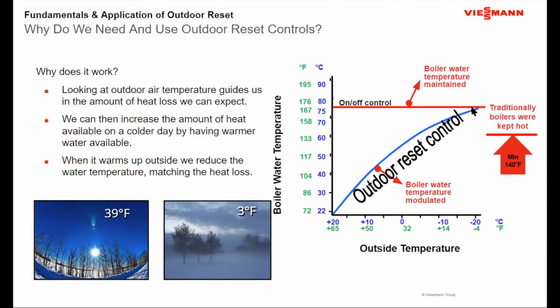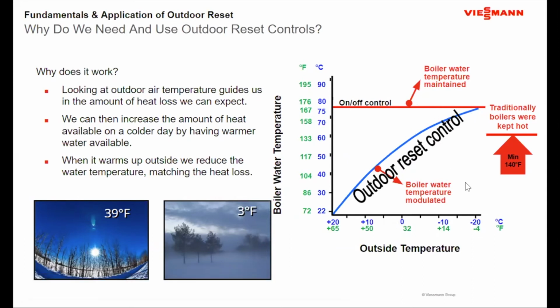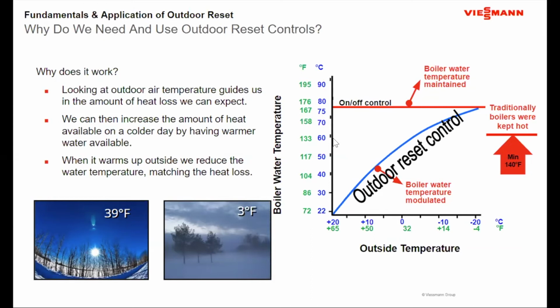And rather than just maintaining the boiler and the system at a constant high temperature and then pulsing the building to maintain room temperature, we now measure the outside temperature. We set up a heating curve, and that heating curve is designed around design conditions. So our design conditions were 0 degrees Fahrenheit, 180-degree water. So the heating curve delivers the design water temperature on the design day, but then as the outside temperature increases, the boiler water temperature decreases proportionally. And by doing that, on a 32-degree Fahrenheit day, we're delivering about 133-degree water temperature. We're staying balanced with the outdoor conditions.